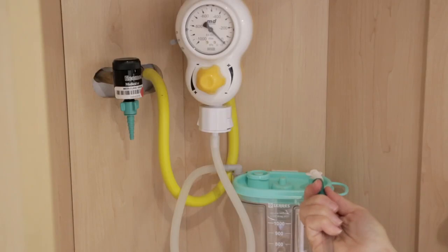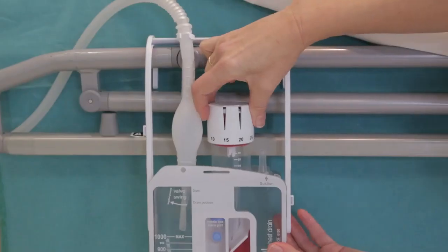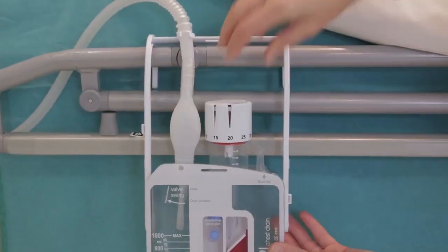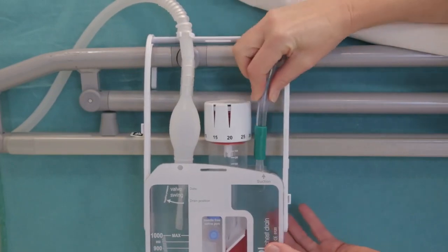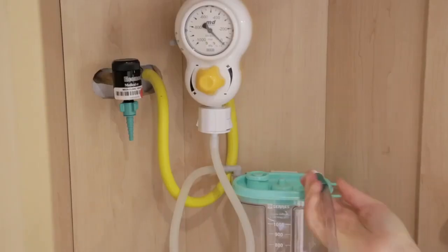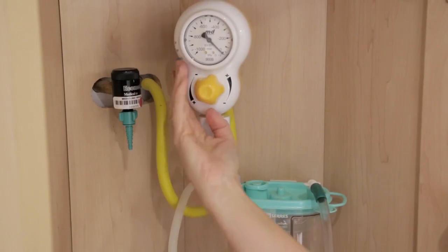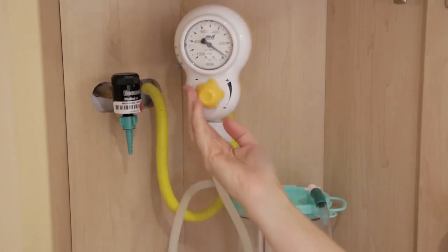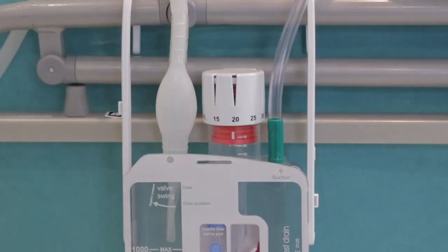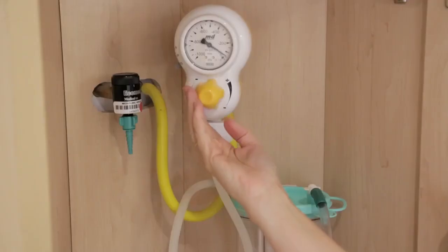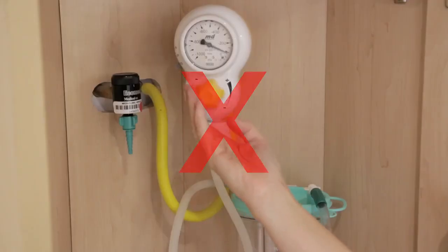Use the Sinapi chest drain for gravity drainage or active suction. To initiate active suction, set the white suction knob to the required value. Connect the tubing from the vacuum source to the suction port. Slowly increase the wall suction from 0 until the red bellows reaches the set value. Do not increase wall suction further, as this will increase noise levels.